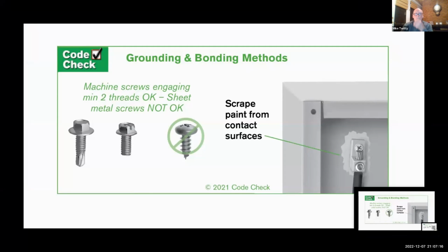Okay, here's another code check, and this is something that you very seldom see. It's supposed to be done: scraping the paint where you make a connection. Let's say you add a ground bar to a sub panel that didn't have an equipment grounding bar. You can buy those ground bar kits and put them in there. They have tapped holes made for them. And I'm guilty of this. I've installed them and didn't scrape the paint, but you're supposed to scrape that paint to get good continuity, because that paint can be an insulator.